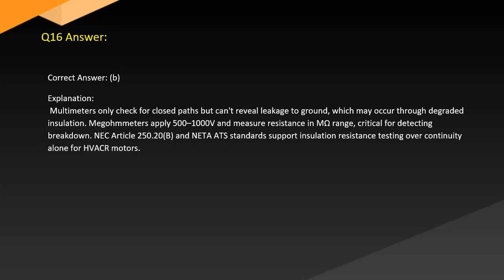Answer. Correct answer: B. Explanation. Multimeters only check for closed paths but can't reveal leakage to ground, which may occur through degraded insulation. Megohmmeters apply 500-1000 volts and measure resistance in the megohm range, critical for detecting breakdown. NEC Article 250.20(B) and NETA standards support insulation resistance testing over continuity alone for HVACR motors.